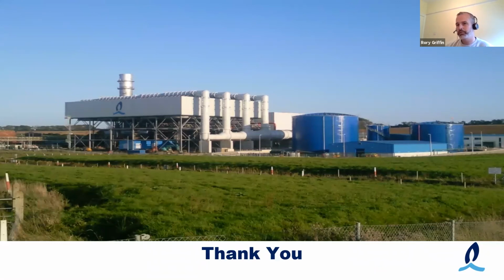There is a 20 kV supply that comes into the site, but that's purely just to feed the house load. So for example, if the main transformer was switched out for maintenance, we can switch over to the local distribution network at 20 kV, but that only feeds the small load like you might have during an outage. So yeah, if the cable trips and we're on a tail feed, we're in serious trouble. It'll be a very severe trip in the plant.